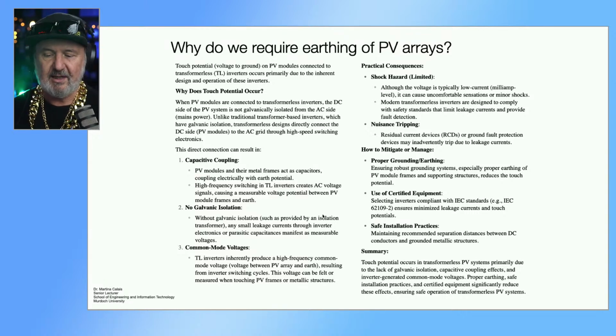I see Charles says, would an RCD on the inverter AC detect this? Yes, though back in 2010, and in fact up to more recent versions of the inverter standard, you were not required, or even encouraged, to put an RCD between the inverter and the main switch inverter supply because of potential false tripping and parallel paths with load circuits. I need to draw all this out to explain it, but we weren't required to do that. In fact, it's the opposite. We're required not to do it.